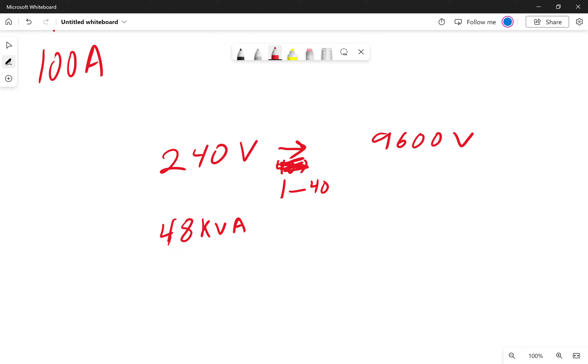That's 200 amps. If I asked what it would be on the secondary side, it's still 48 kVA, since volt amps stay the same. We've moved our voltage up by 40, and there are two ways to find the answer: take 48,000 divided by 9,600, or, since I know the ratio went up by 40, divide the 200 amps by 40.